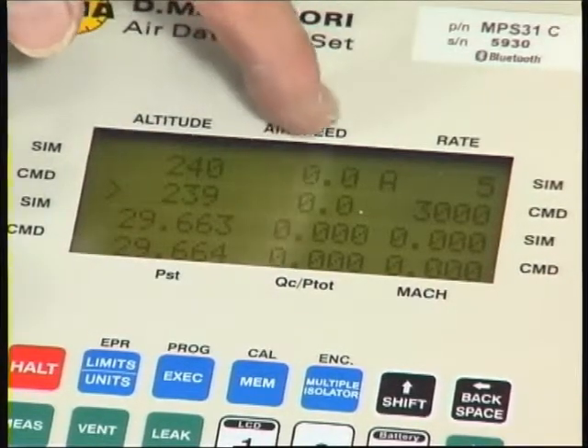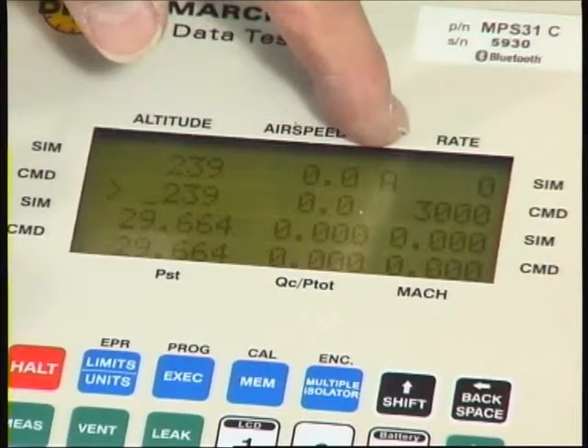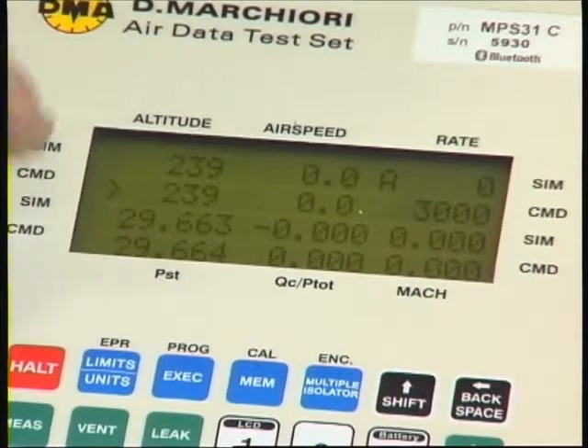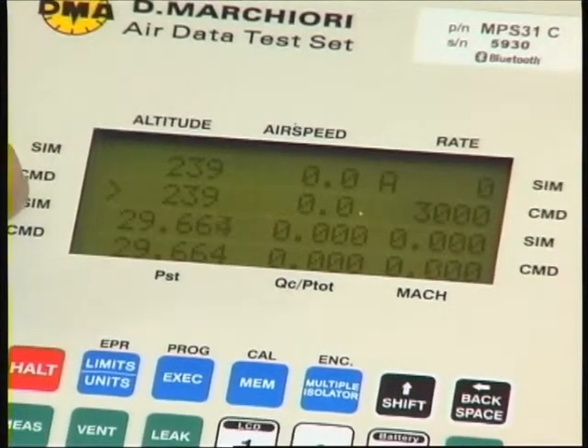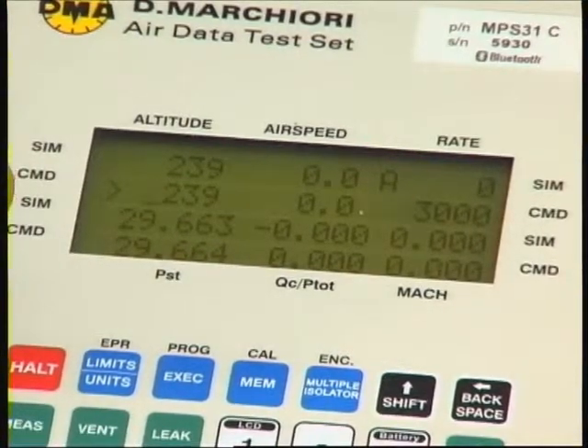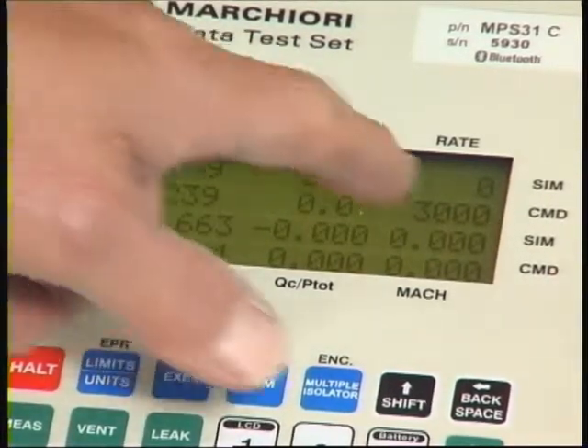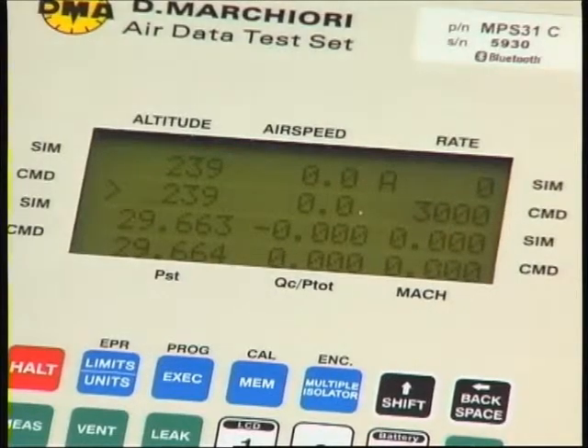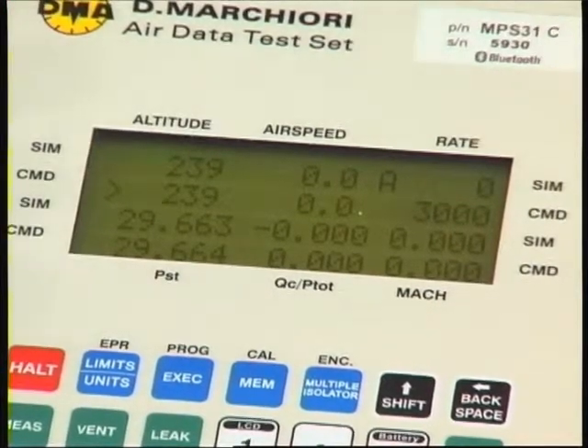The airspeed is equivalent to zero knots and the altitude rate is effectively zero because we're not going anywhere. Immediately under the simulated line is the command line, which enables you to call for a new value. The command altitude is exactly the same as the simulated actual value, as we would expect. Similarly with airspeed. The command rate value is 3000 by default when you turn on the instrument, until you give it an altitude and tell it to move.